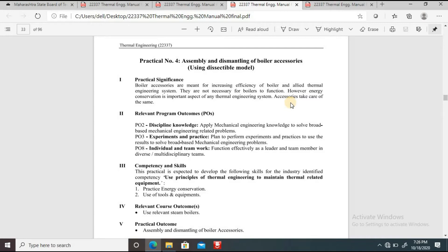The basic difference between boiler mountings and accessories is: boiler mountings are essential for the safety of the boiler, whereas boiler accessories are only meant for increasing the efficiency of the boiler. We can run the boiler without boiler accessories, but as per the Indian Boiler Act, we cannot run the boiler without boiler mountings. So if asked to choose between the two, give first preference to boiler mountings because they are compulsory.